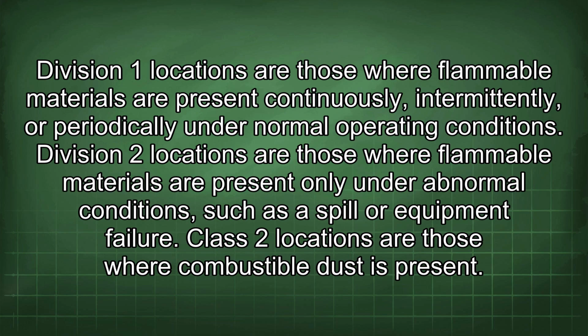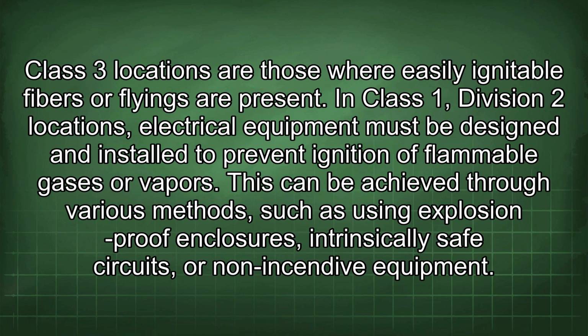failure. Class 2 locations are those where combustible dust is present. Class 3 locations are those where easily ignitable fibers or flyings are present. In Class 1, Division 2 locations, electrical equipment must be designed and installed to prevent ignition of flammable gases or vapors. This can be achieved through various methods, such as using explosion-proof enclosures, intrinsically safe circuits, or non-incendive equipment.